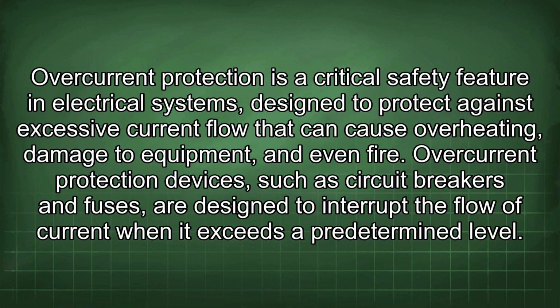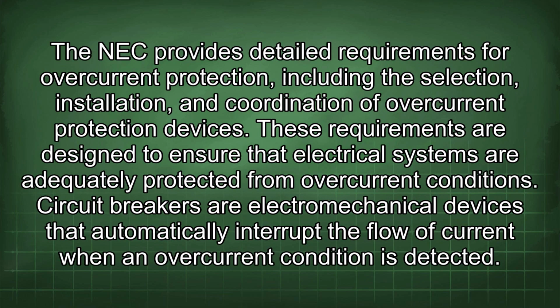Overcurrent protection is a critical safety feature in electrical systems, designed to protect against excessive current flow that can cause overheating, damage to equipment, and even fire. Overcurrent protection devices, such as circuit breakers and fuses, are designed to interrupt the flow of current when it exceeds a predetermined level. The NEC provides detailed requirements for overcurrent protection, including the selection, installation, and coordination of overcurrent protection devices. These requirements are designed to ensure that electrical systems are adequately protected from overcurrent conditions.